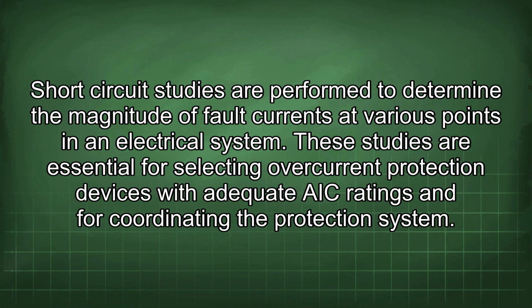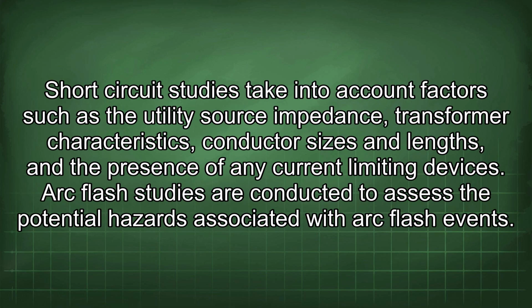Short circuit studies are performed to determine the magnitude of fault currents at various points in an electrical system. These studies are essential for selecting overcurrent protection devices with adequate AIC ratings and for coordinating the protection system. Short circuit studies take into account factors such as the utility source impedance, transformer characteristics, conductor sizes and lengths, and the presence of any current limiting devices.